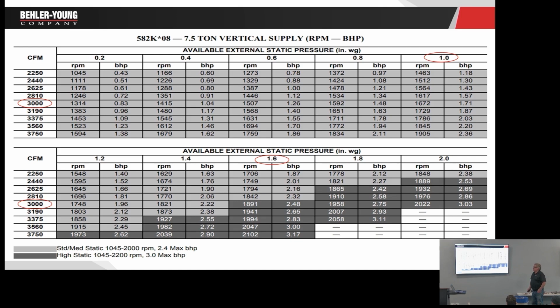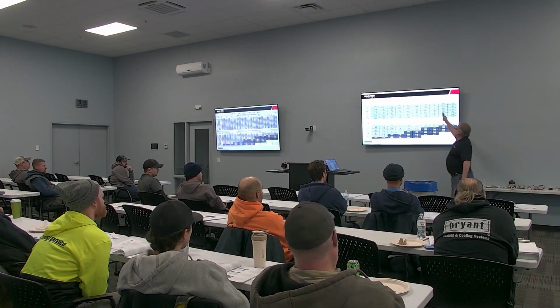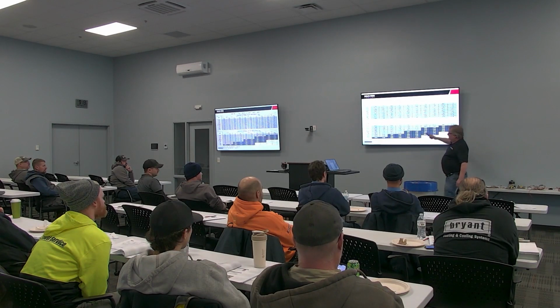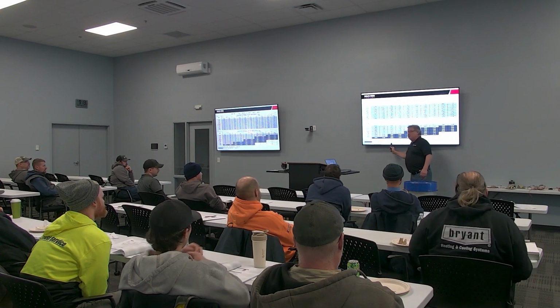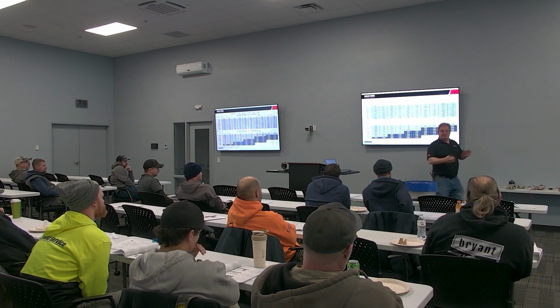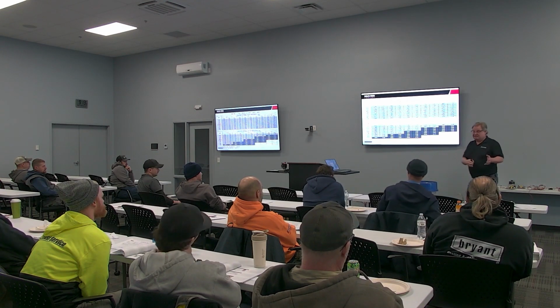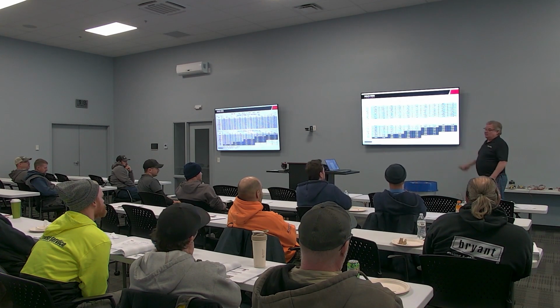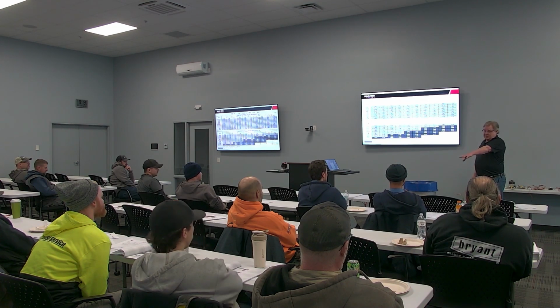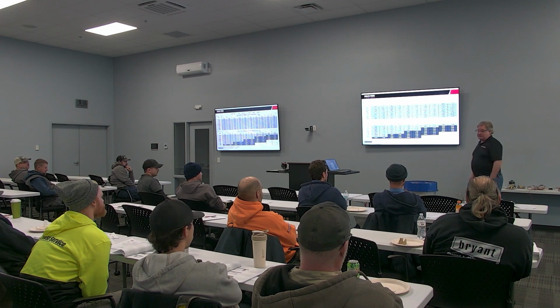Okay. The one I talked about with the 0.8 inches of static with the curb adapter, I went to this chart. I could plainly see my problem, and you can see what happened is the motor horsepower changed. So I was able to go to the high static motor. It was belt drive, and I was able to change it, and the unit worked out fine then. This one is a little different, right? Because I can't just change the motor because the motor's different.